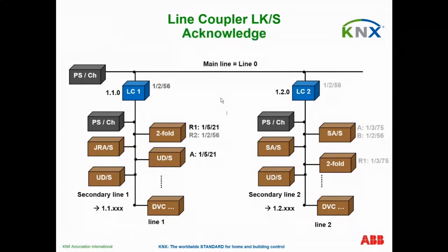And very important to remember as well is how KNX telegrams are acknowledged in a network. If a telegram does not get acknowledged or it receives a not acknowledged signal, every device will send the telegram three times. It does this three times to make sure that it does not flood the network and just keep sending unanswered telegrams onto a network. It's another important thing to remember. However, we have to see where those acknowledgements come from.